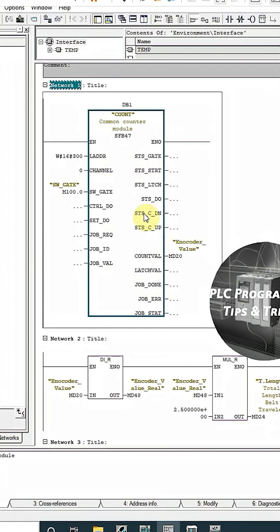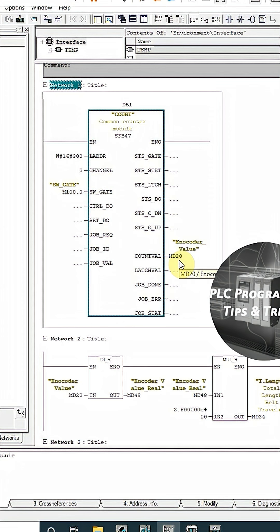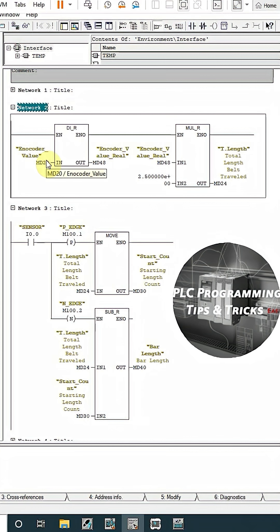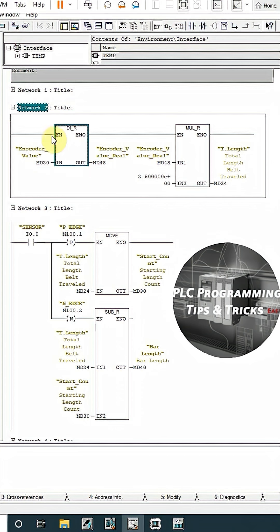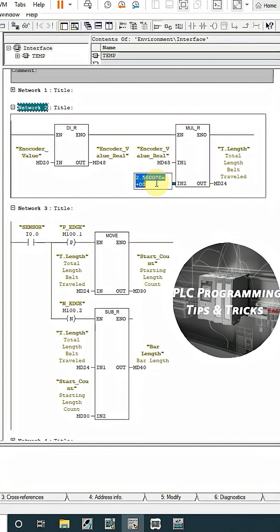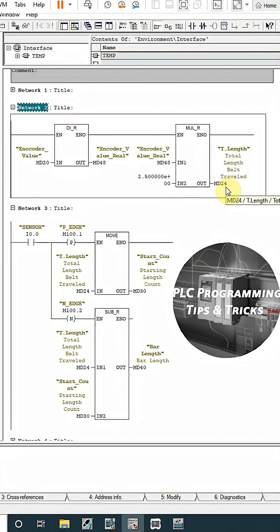In the last lesson, we have learned how to connect an encoder with the PLC and how to read its value. So our encoder value was coming at MD20 data register. In the next network, we will convert the encoder value to the real value using this conversion instruction. Next, we have to multiply this real value to the factor 2.5 which we have calculated earlier. The value will be stored into MD24 which is total belt length travel.